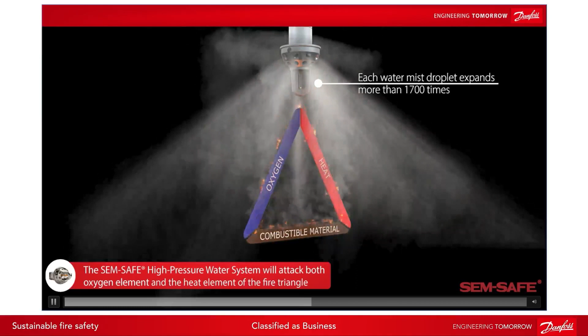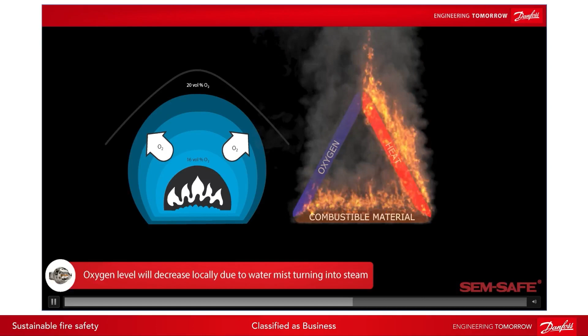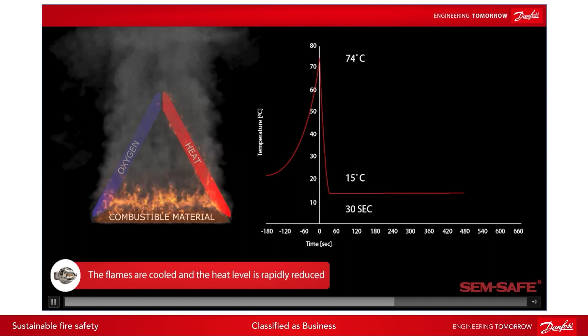So what happens? A small droplet becomes steam near the fire, and with that it expands 1700 times, and then it reduces the oxygen. So this is how we reduce the oxygen, only near the fire. So it's very important that we don't need a concealed area like a gas extinguishing system to reduce the oxygen. The water droplets will just reduce the oxygen concentration near the fire seat. So yes, we can take the next slide.